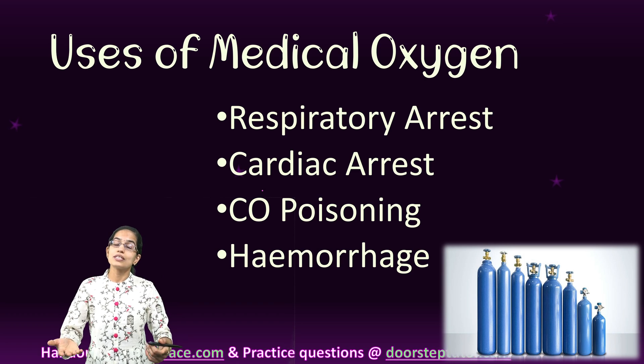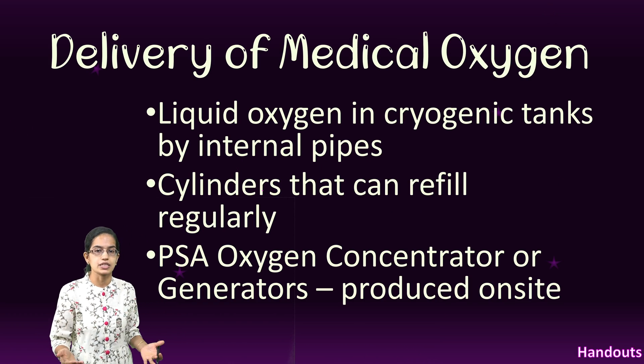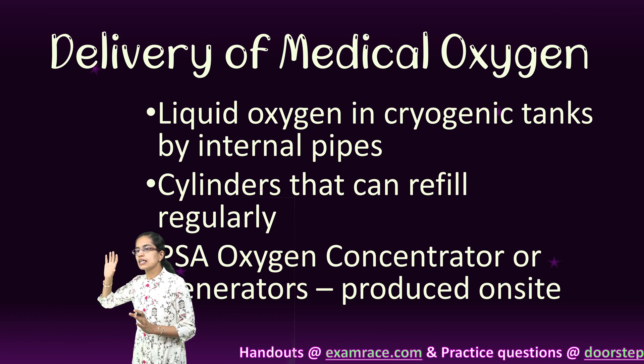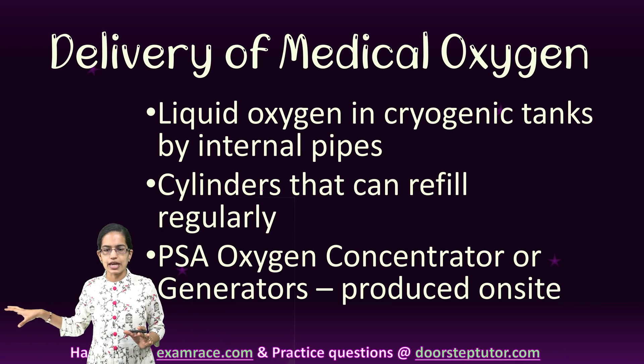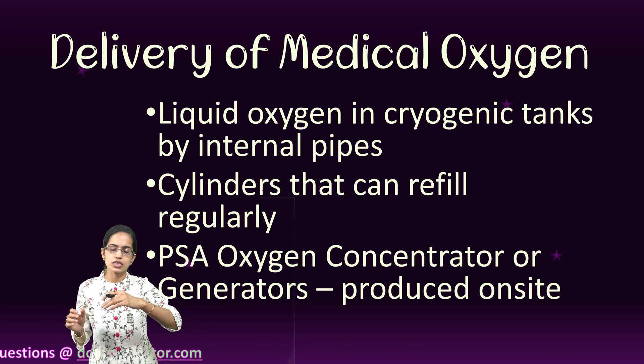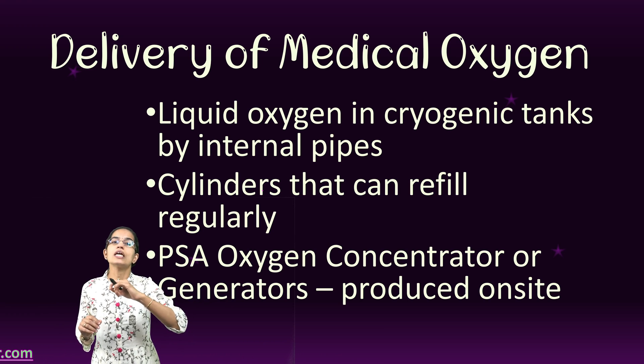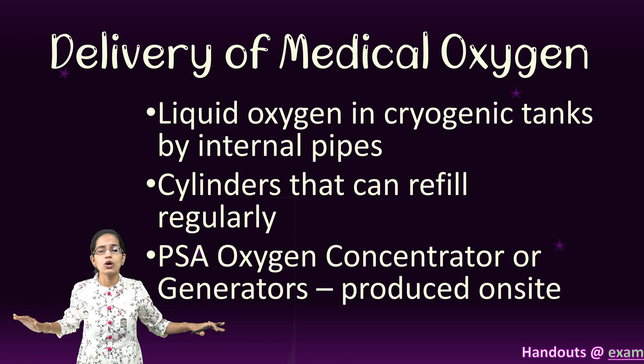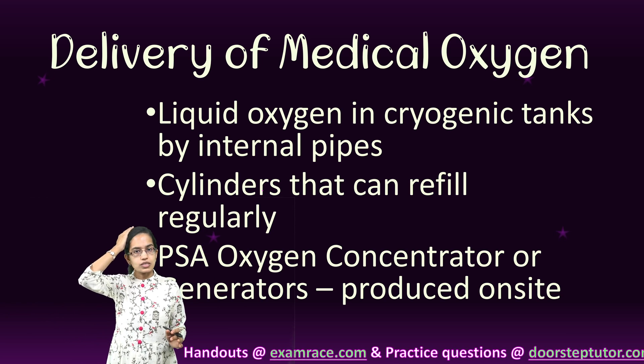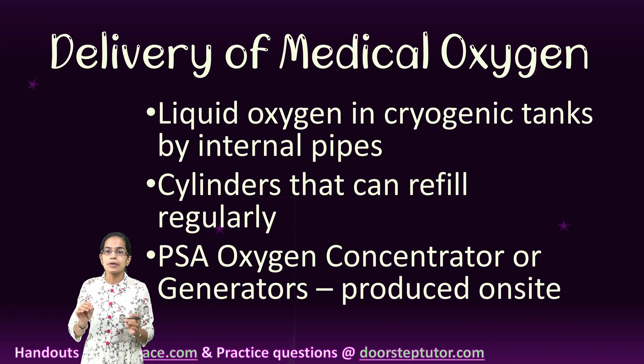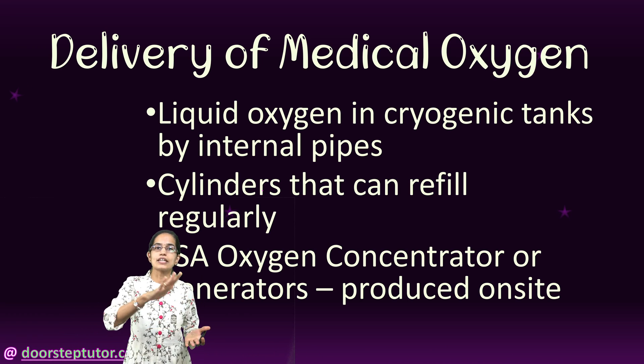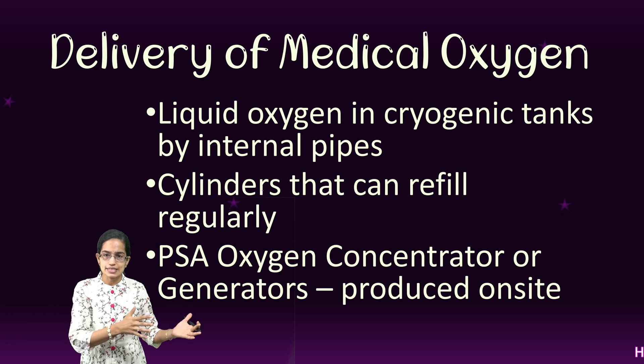Medical oxygen is delivered to individual patients through primarily three ways. First, liquid oxygen is prepared at the site and through cryogenic tanks, this liquid oxygen reaches hospitals through internal pipelines — the whole hospital has the pipeline infrastructure for this. The second way is through cylinders; once the oxygen is consumed, they are sent for refilling, similar to the LPG gas cylinders that we use.